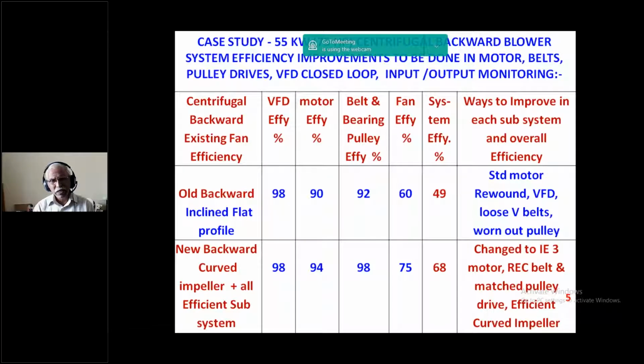So automatically, the efficiency of the impeller itself is only around 60%. VFD efficiency is around 98%. The motor efficiency at 55 kilowatt is around 90%, and the belt, bearing and pulley have 8% loss. So totally, we have to concentrate on the system efficiency, which is only at 50%.